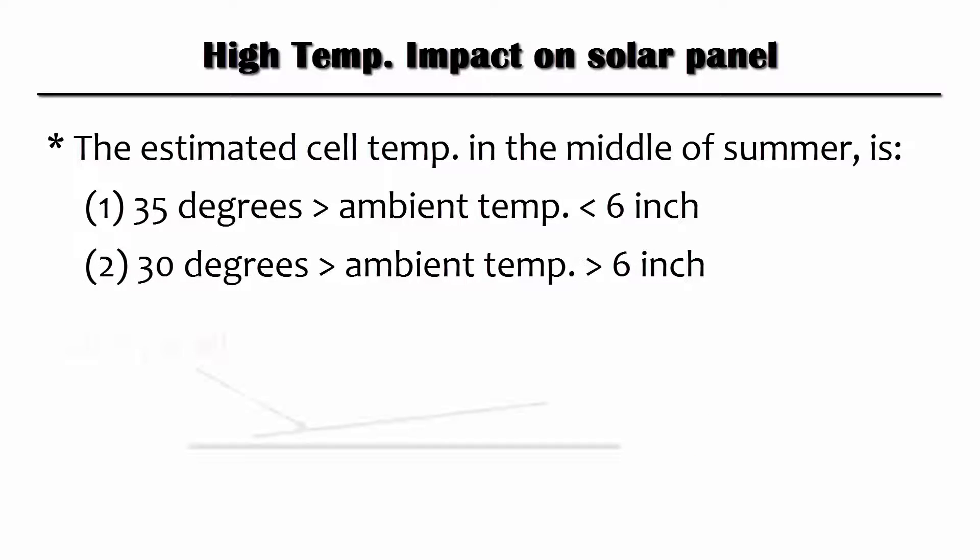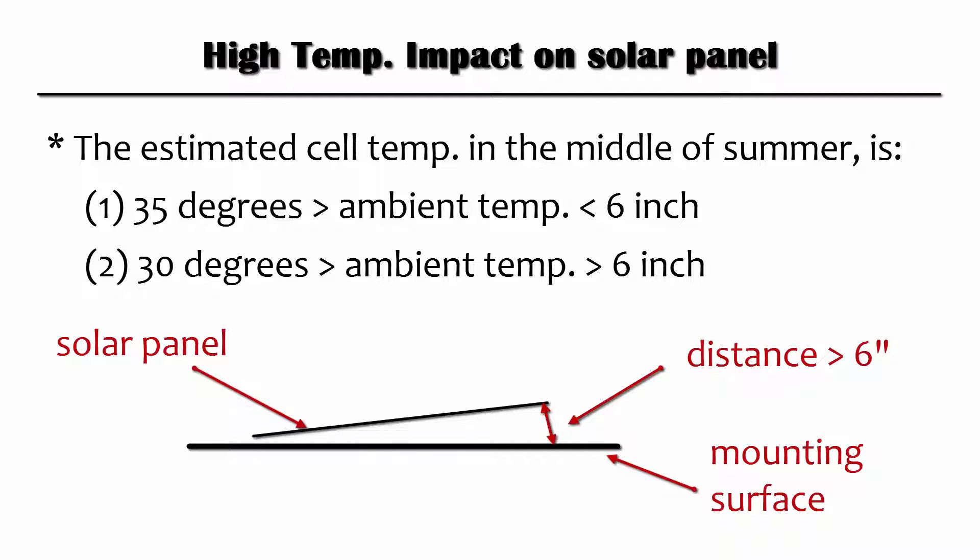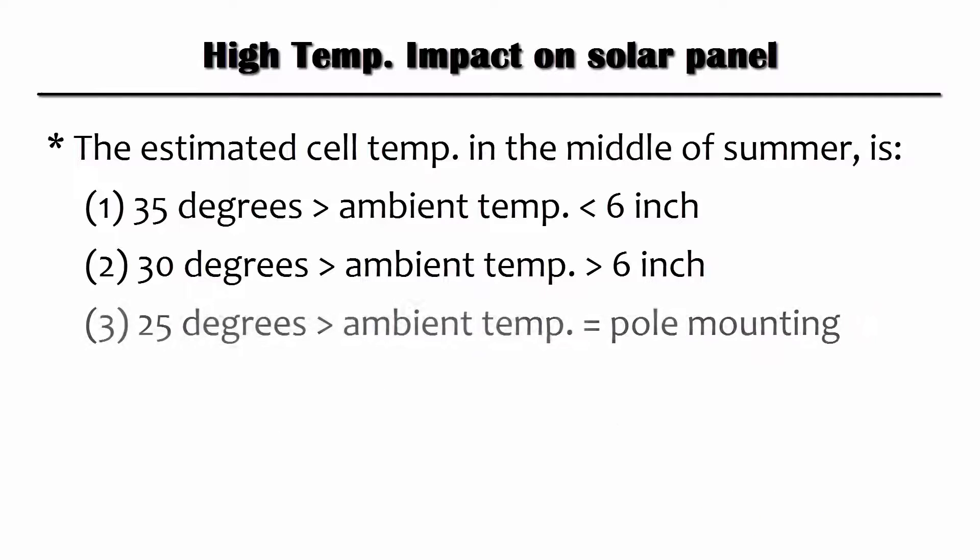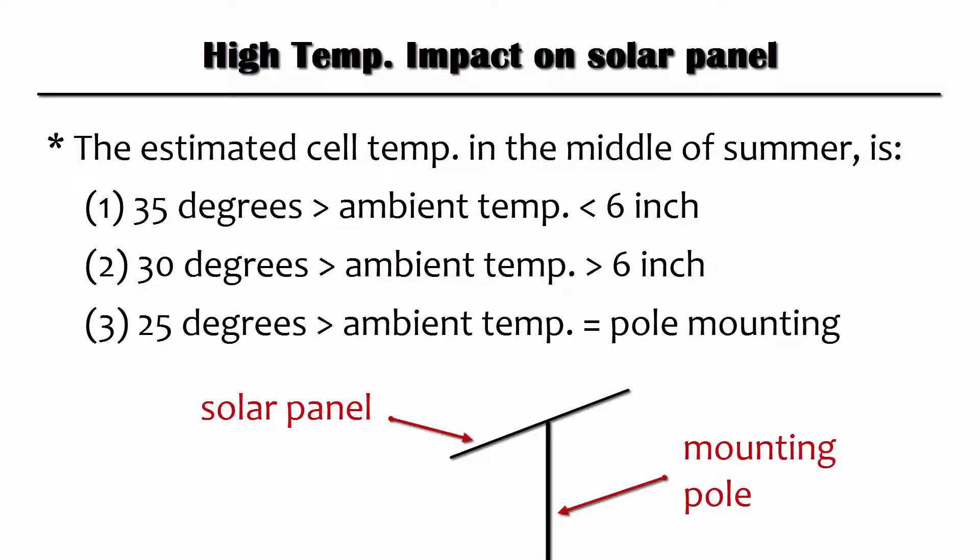It's 30 degrees above ambient if the distance is more than 6 inches, and 25 degrees if the panel is on top of a pole.